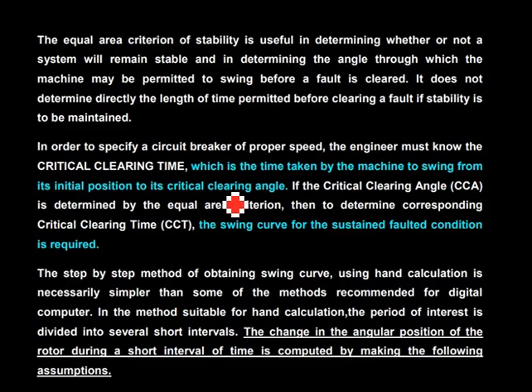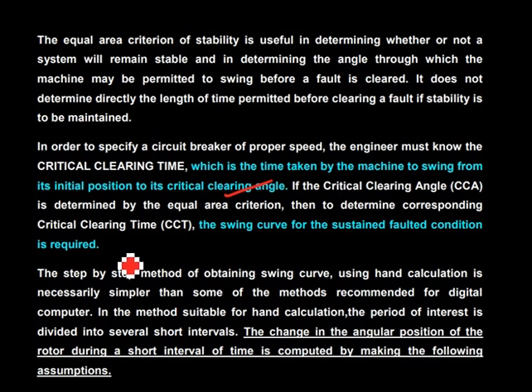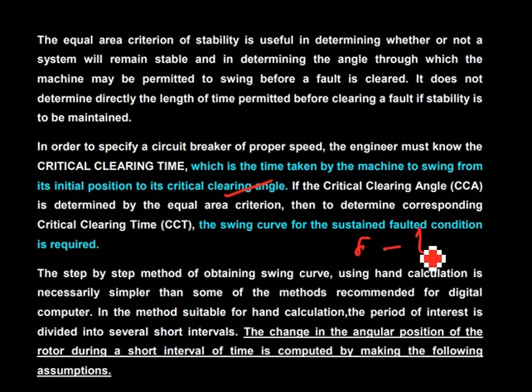The critical clearing angle is one important concept — it is the maximum load angle at which a fault can be cleared in order to keep the system stable. If you go beyond that point, the system may not remain in a stable operating condition. Corresponding to the critical clearing angle, there is a clearing time, and you need a relationship between delta and time.